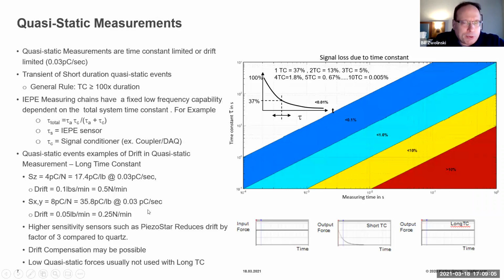And here's just an example of quasi-static again. The drift component that I talked about is roughly around 0.5 Newton per minute. So if you're measuring hundreds or thousands of newtons over a minute, that's insignificant. And a lot of times you can compensate for this as well. So even for static or quasi-static events like thrust, it's usually not an issue when measuring with piezoelectric technology.